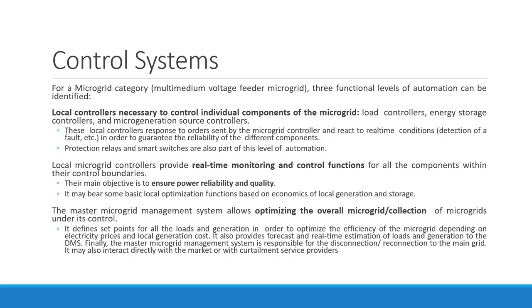So the master microgrid management system is going to allow optimizing the overall microgrid or collection of microgrids under its control. It defines set points for all the loads and generators to optimize the efficiency of the microgrid, which will depend on the electricity prices and local generation cost. Already we said, suppose your microgrid only consists of a diesel generating unit, and the power which is available from the main grid is cheaper than what you are producing from the distributed generation or diesel generators. So it's better to draw the power from the main grid instead of producing your own. So that's why we are saying that it is going to optimize the efficiency of the microgrid, and the basis will be electricity price and local generation cost.